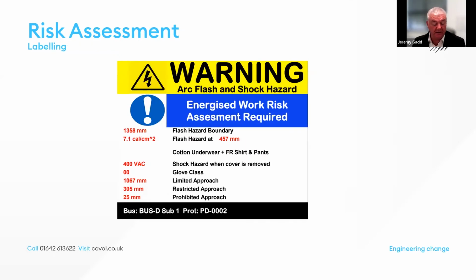So we end up with the labelling, which determines what the results of that arc flash study have determined. And this denotes incident energy levels and arc flash boundaries. Once incident energy levels are known, then appropriate PPE can be specified. And there's a note there that they use cotton underwear and FR shirts and pants.